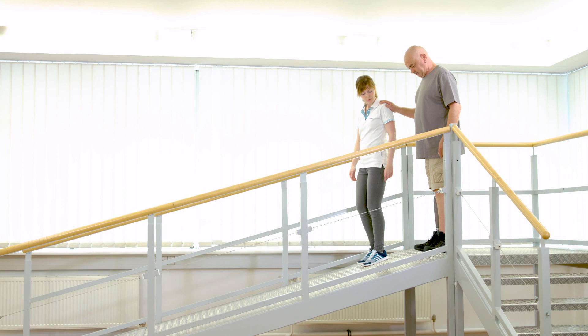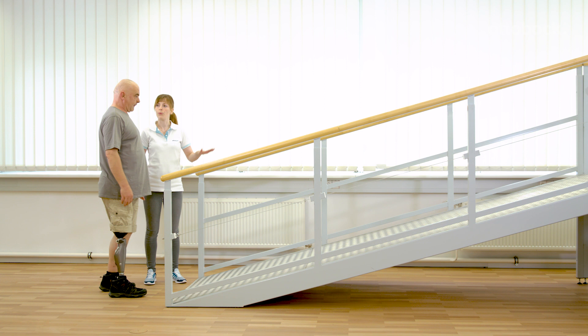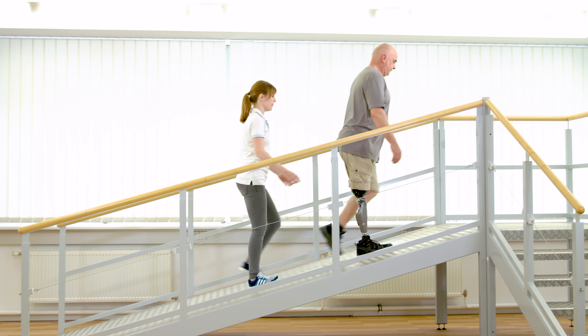The legs can only be equally loaded if the stance flexion resistance is properly adjusted. The selected resistance acts the same in every situation where the knee is flexed and under load. Besides walking downhill, the situations are sitting down and walking downstairs.